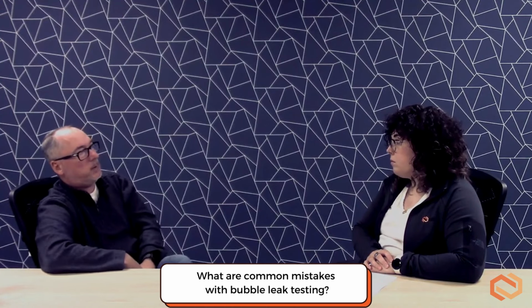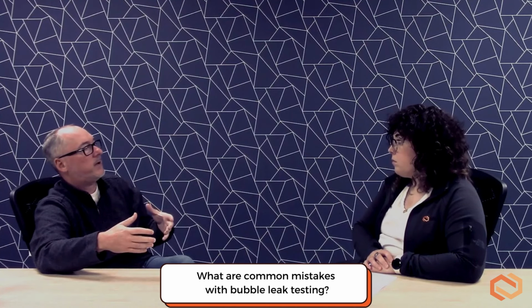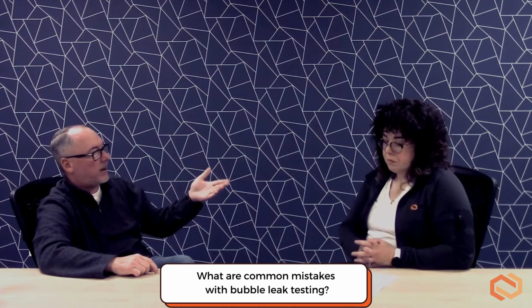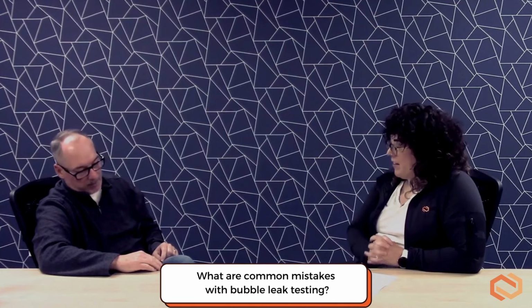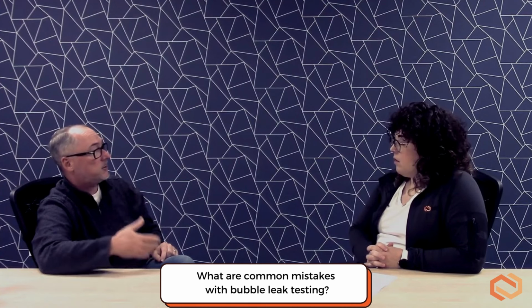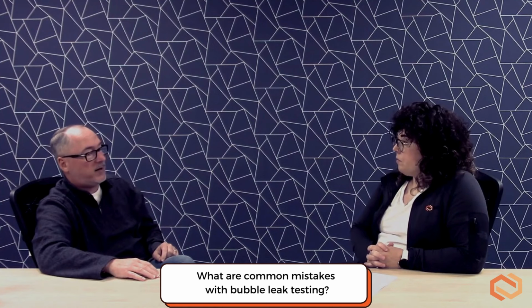So usually at DDL, when we see something like that coming through the Tyvek, you've got to run a secondary test on it. Sure. I'm sure you've seen a lot of protocols say that as well. Absolutely, supported with dye leak. Yes. If a perceived failure in the Tyvek is there, execute dye penetration on that perceived area. Yep. And I'll say 99.9%, it's not a failure.